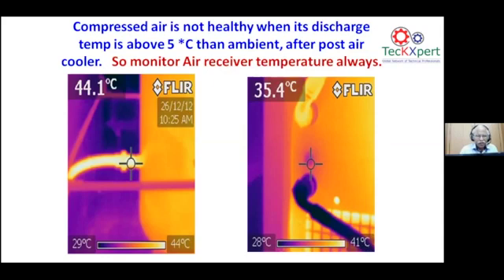So monitoring the air receiver's temperature has become mandatory now in many of the industries. This is an add-on temperature gauge with an indication of what is the normal temperature and what is high temperature. This can be had on the temperature gauge assets, and you can give a remote indication also, an audio visual alarm. And on the receiver, the same thing. What is at the ambient and what is the plus or minus 5 degrees is the inlet to outlet temperature difference that is happening on the refrigerator dryer.